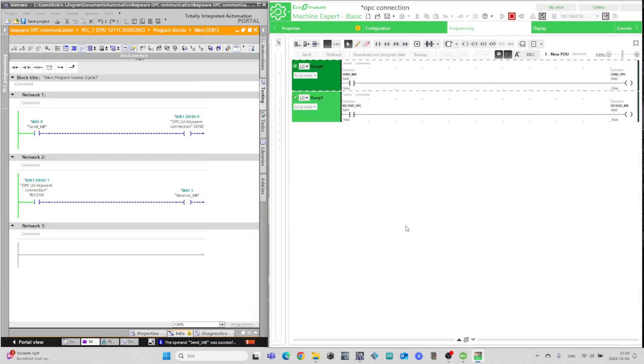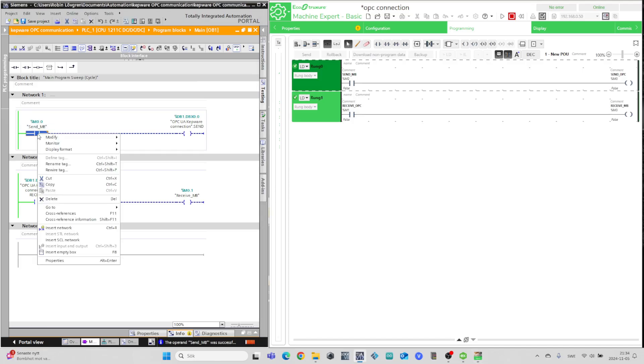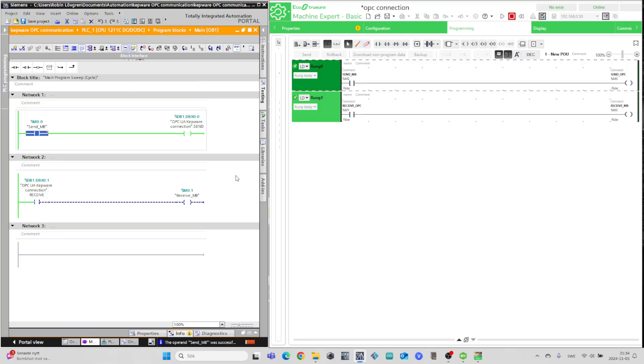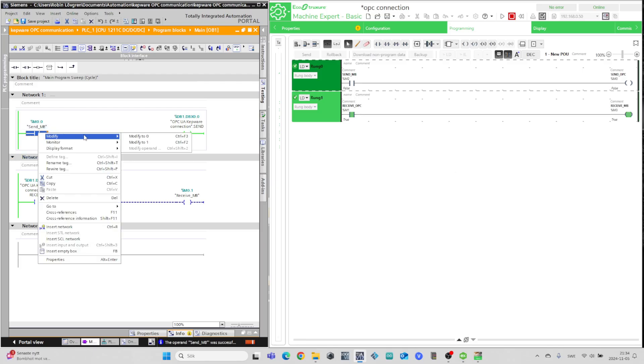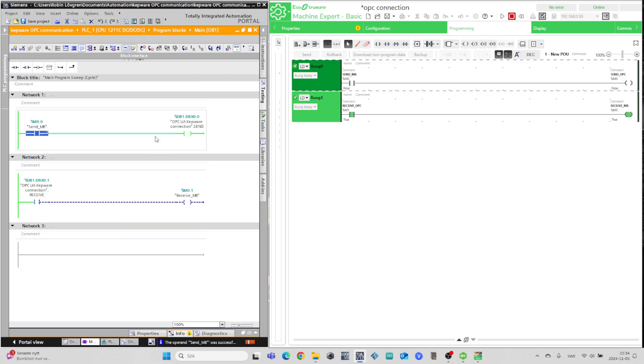I will now go online on both PLCs and test out the connection. If I now trigger the send tag from TIA Portal, the receive tag from MachineExpert will trigger. And vice versa when I trigger from MachineExpert.